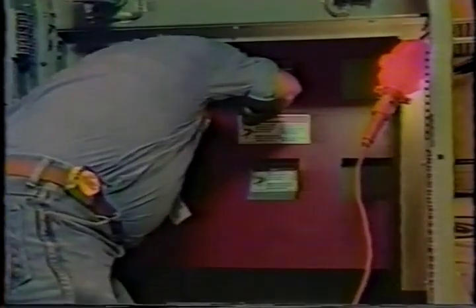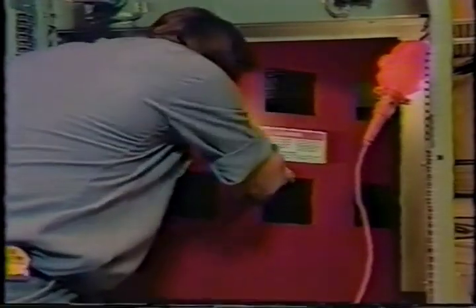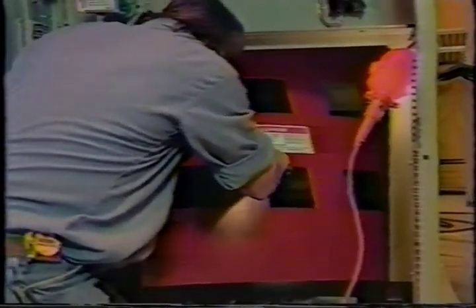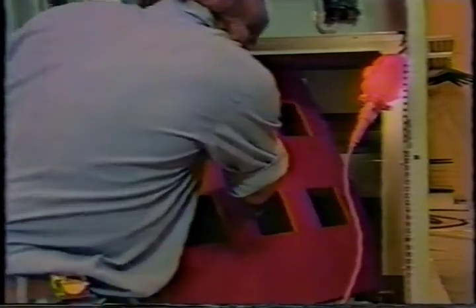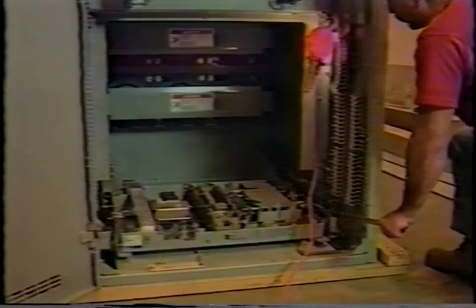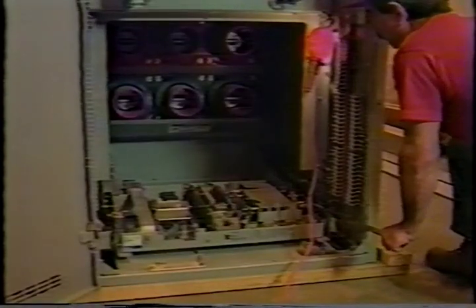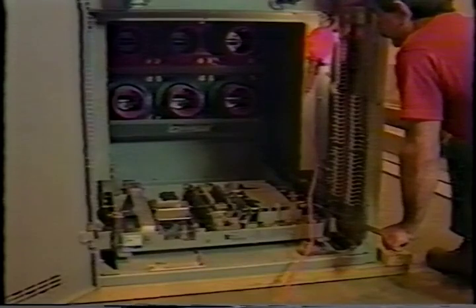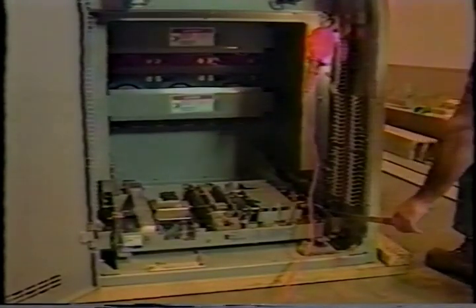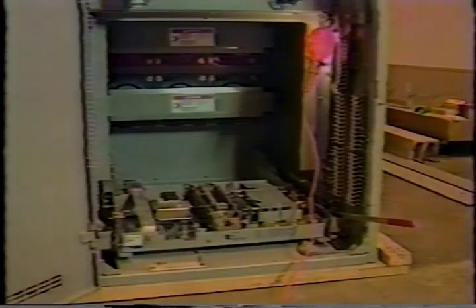In VacCLAD W switchgear, both the stationary main disconnecting contacts and the ring-type current transformers are located behind the glass polyester CT barrier. Since the upper and lower contacts and transformers are easily exposed, caution must be exercised. Do not expose any contacts or transformers unless all upper and lower high voltage parts are de-energized. Failure to do so could cause personal injury or property damage.